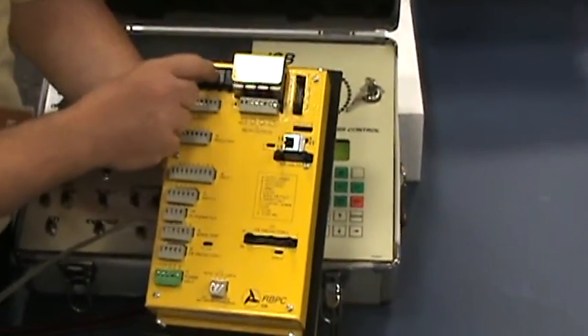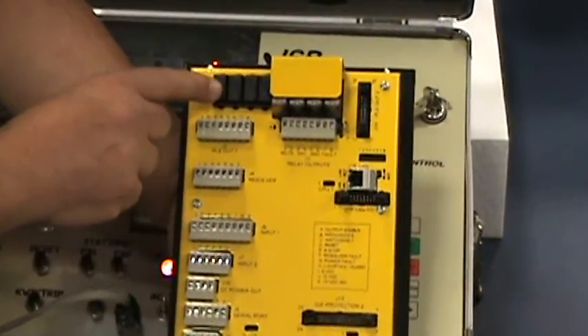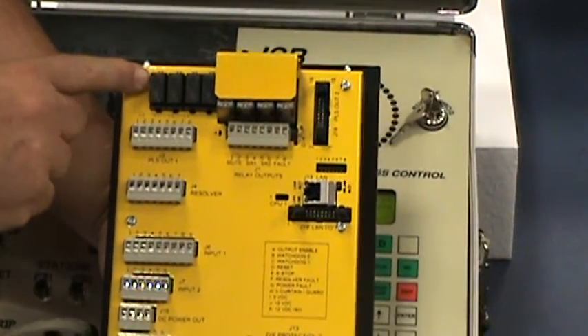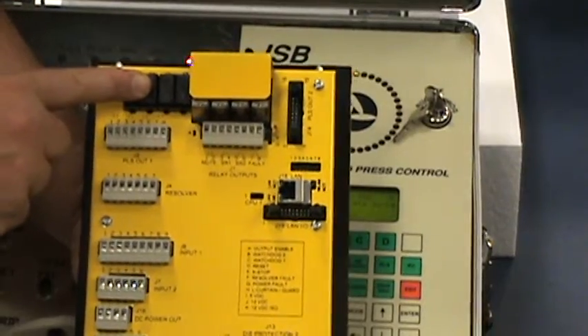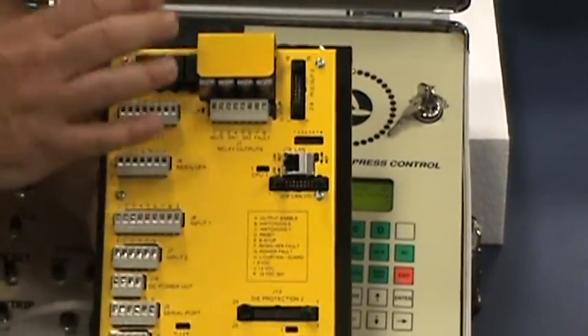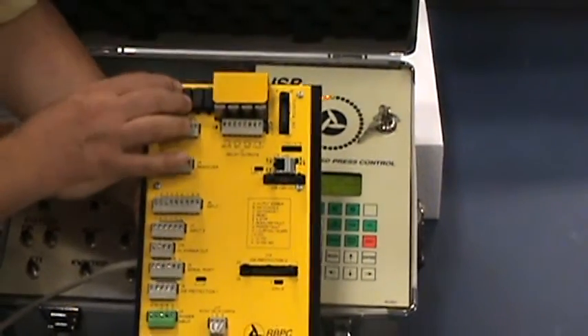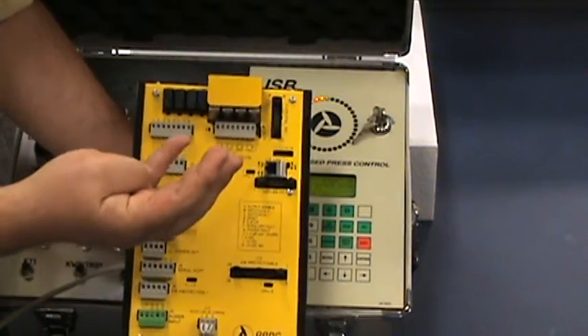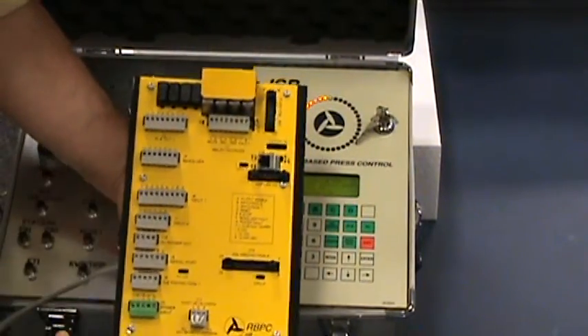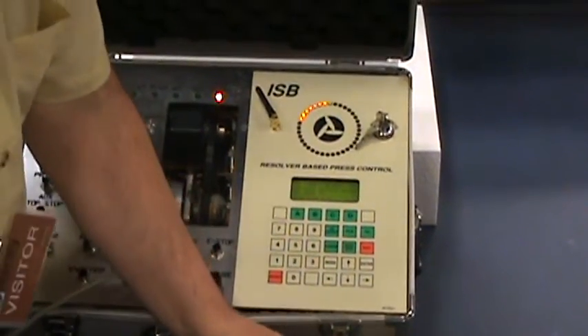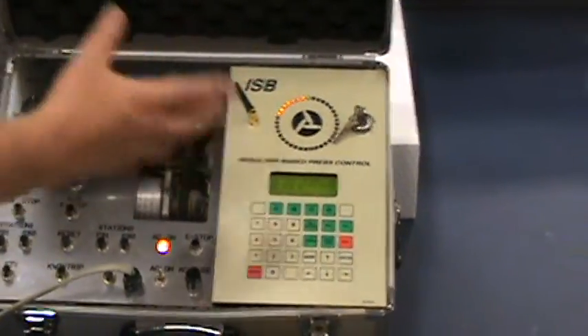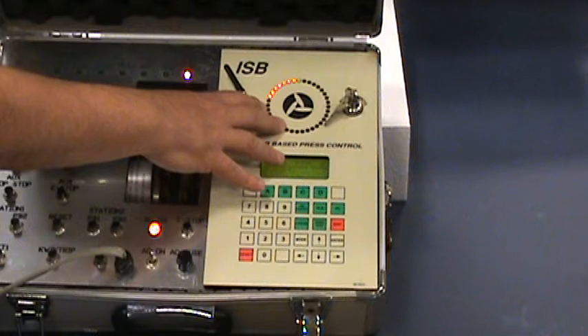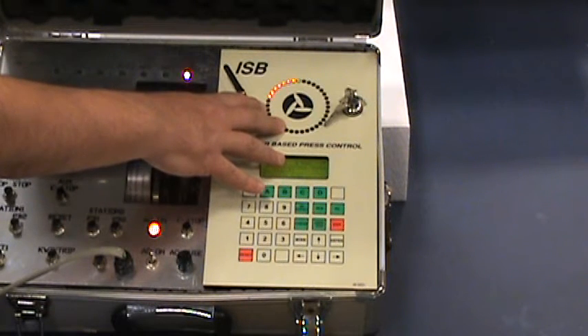But right next to them, there are four little black relays. These are unpluggable, field serviceable relays. What these are, are the four built-in programmable limit switches. Every RBPC comes with four built-in programmable limit switches. These can be used to turn on and off pieces of equipment such as your air blow off, your spray lubricator, your scrap chopper, your feed. So instead of putting a limit switch and turning it on and off with a crank that you have to climb up and down the ladder to make adjustments, you can actually use the programmable limit switches in here to turn on and off external pieces of equipment. They're there.